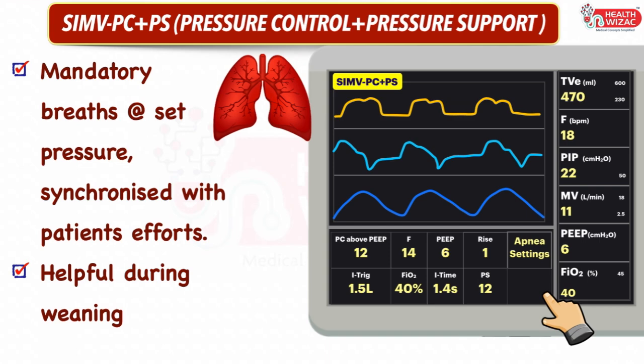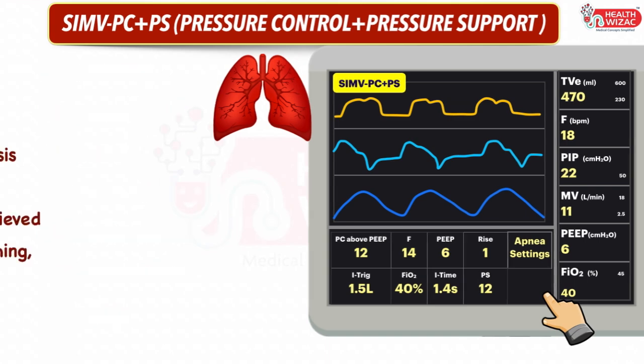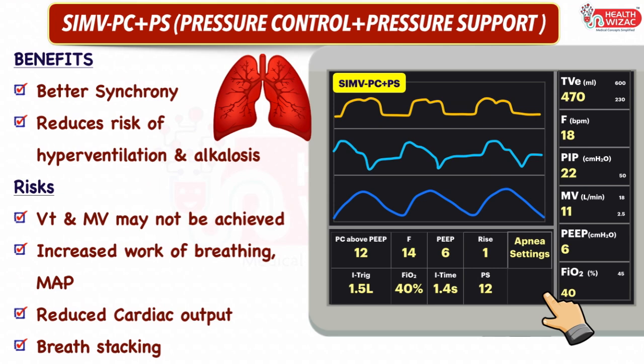This mode is very helpful during the weaning process. Advantages include better synchrony with the patient, which reduces the risk of hyperventilation and alkalosis. Disadvantages include non-delivery of desired tidal volume and minute ventilation, increased work of breathing, rise in mean airway pressure, reduced cardiac output, and breath stacking.